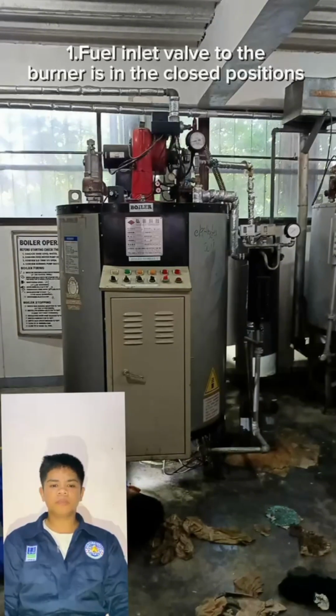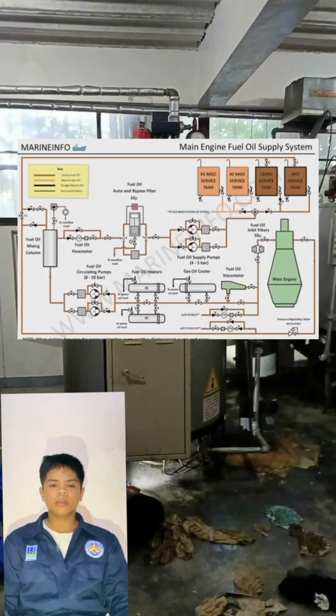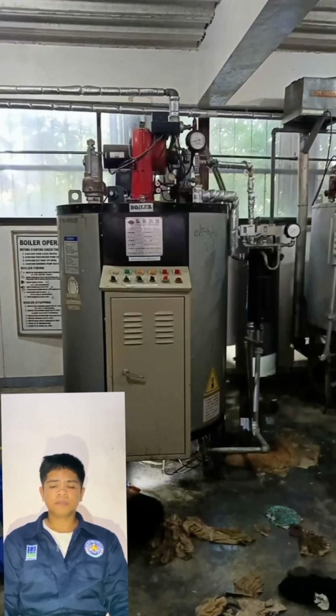The first is the fuel inlet valve to the burner being in the closed position. The fuel line for the boiler burner consists of several valves located at the fuel tank: the suction valve, the discharge valve, or the valve before the boiler burner. Any of these can be in the closed position, resulting in starvation of the fuel.